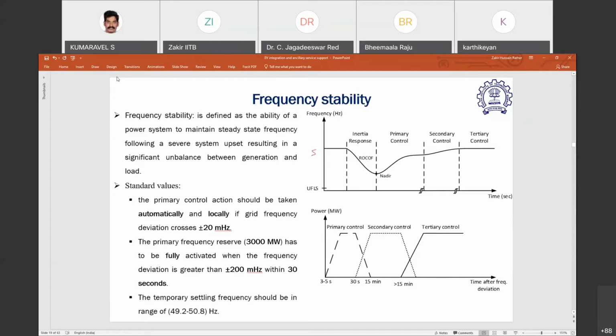Let us say we have this 50 hertz frequency. Grid is operating under normal conditions till this point. All perfect till the instant of the disturbance. Now suddenly there is a generation outage at this instant. Let us say, for example, in the Indian grid, there is a 500, 800 megawatt generation outage. It is unplanned. There is a fault, the generator tripped, or there is a maloperation of the protection and the generator tripped. Unplanned outage of the generation.